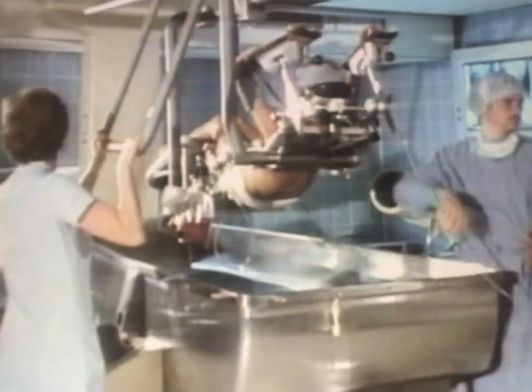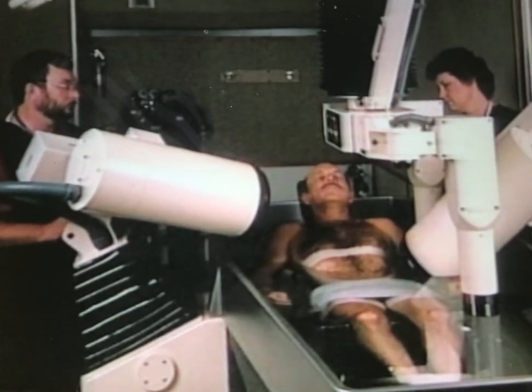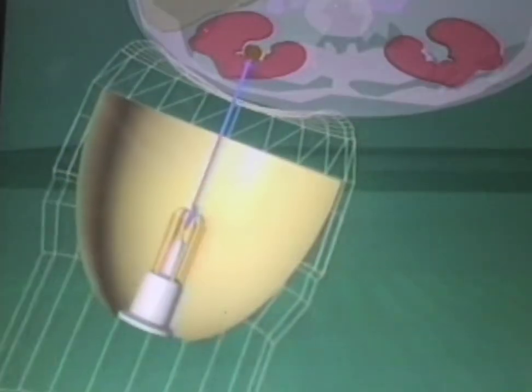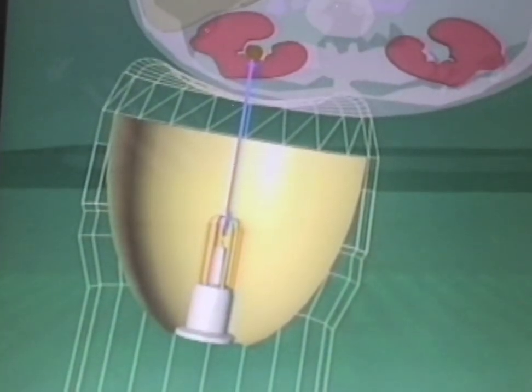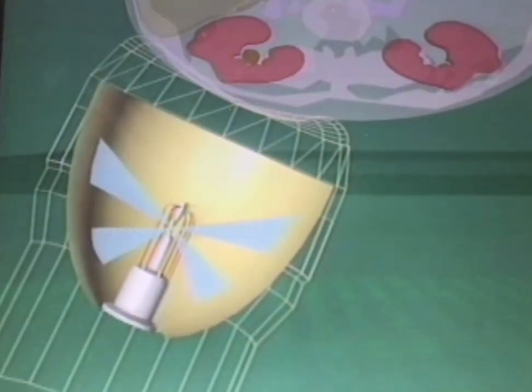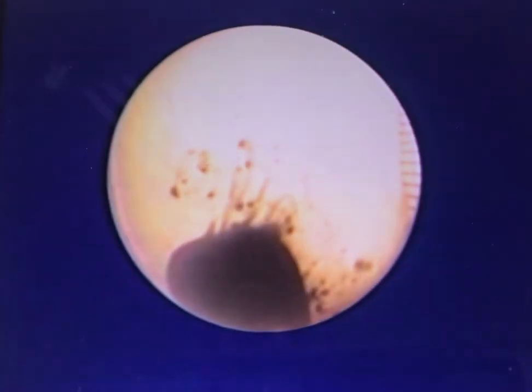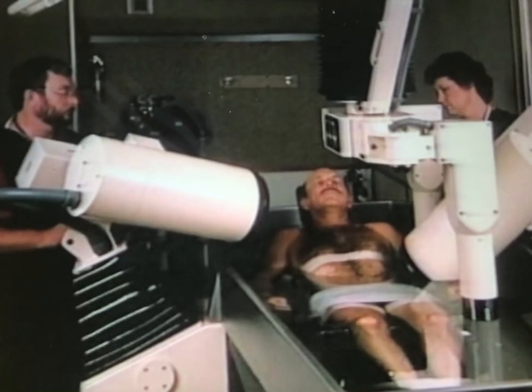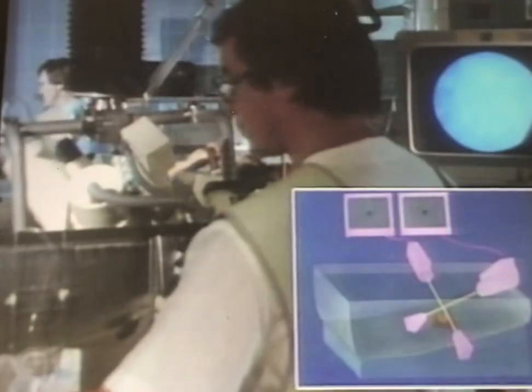In completely unbloody extracorporeal lithotripsy, the essential thing is exact positioning of the kidney stone in the body at the focal point of the shock wave ellipsoid. This is facilitated by a stretcher, which is hydraulically adjustable in extremely small steps, and on which the patient is strapped so that the kidney area of the back lies exposed above the half-open ellipsoid. The shock wave is generated in the first focal point with the help of the shock wave electrode. Two X-ray image amplifiers permit precise three-dimensional positioning of the stretcher so that the kidney stone is placed exactly at the point of maximum effect of the shock wave.